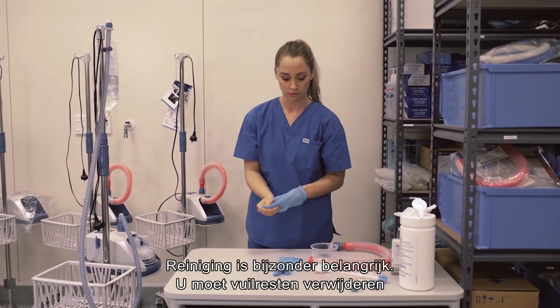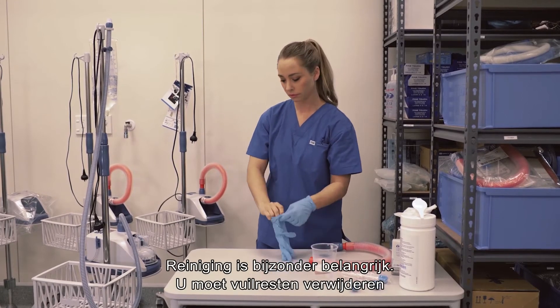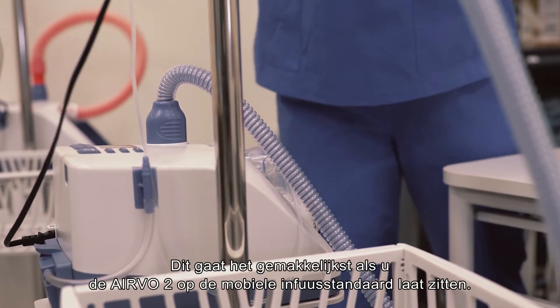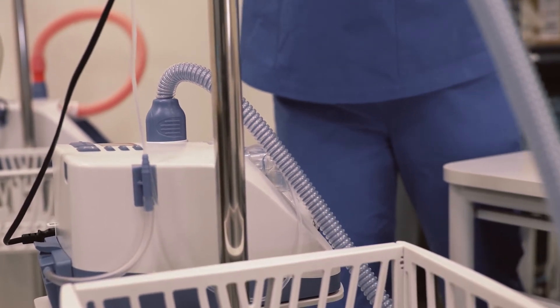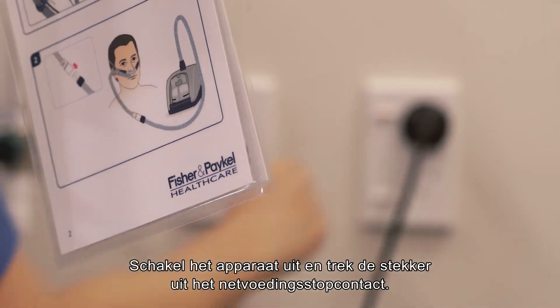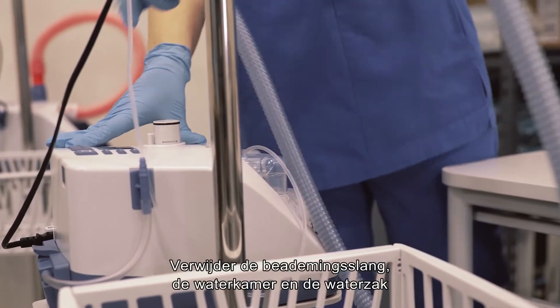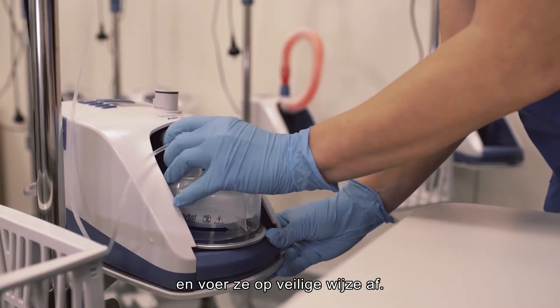Cleaning is particularly important. You need to remove debris so that disinfection works effectively. It's easiest if you leave the AIRVO 2 on the mobile pole stand. Switch off the unit and unplug from the mains utility power socket. Remove the breathing tube, water chamber and water bag and safely dispose of them.